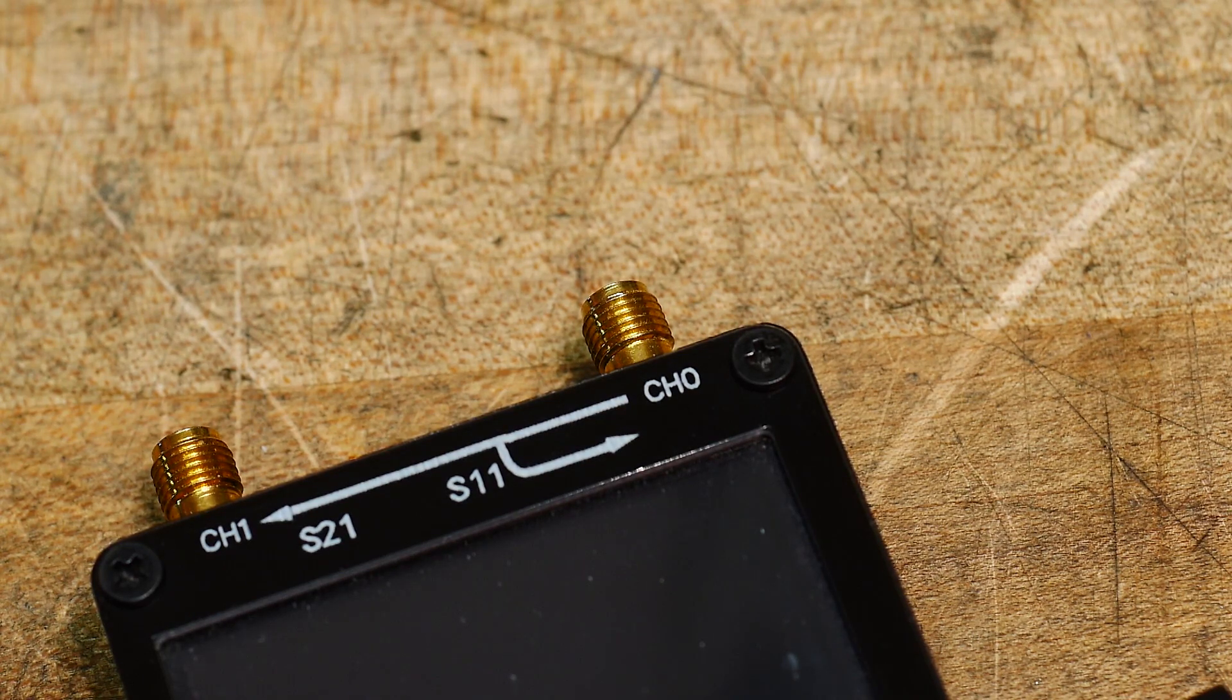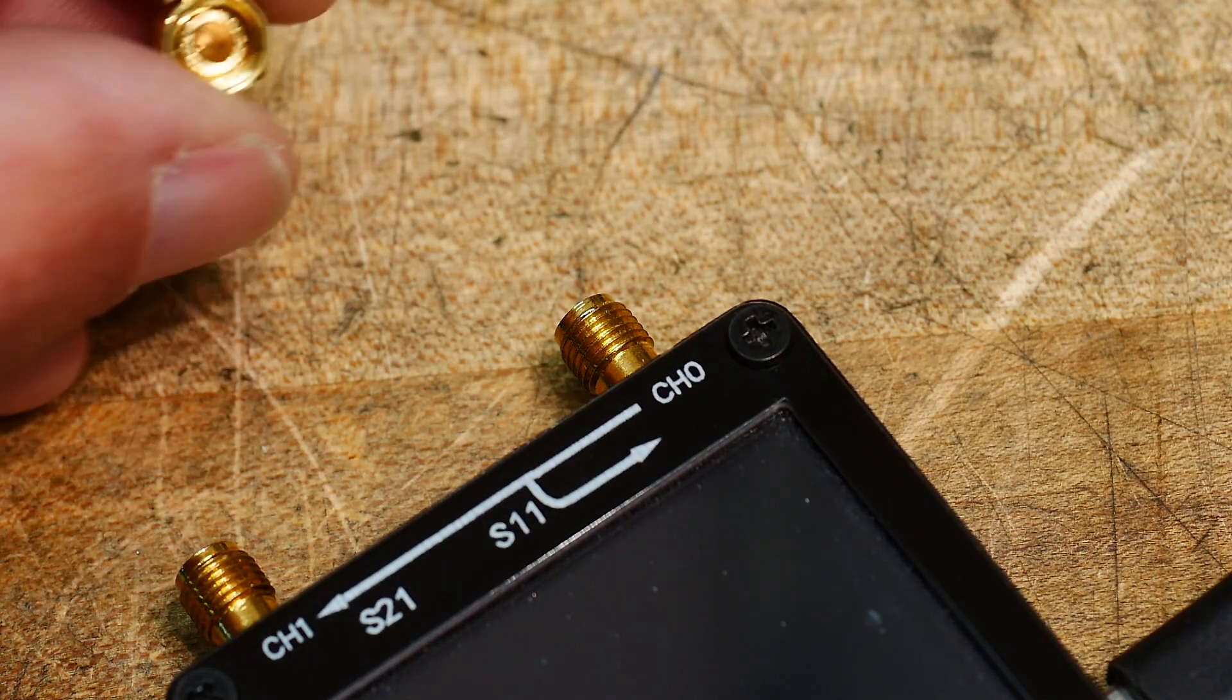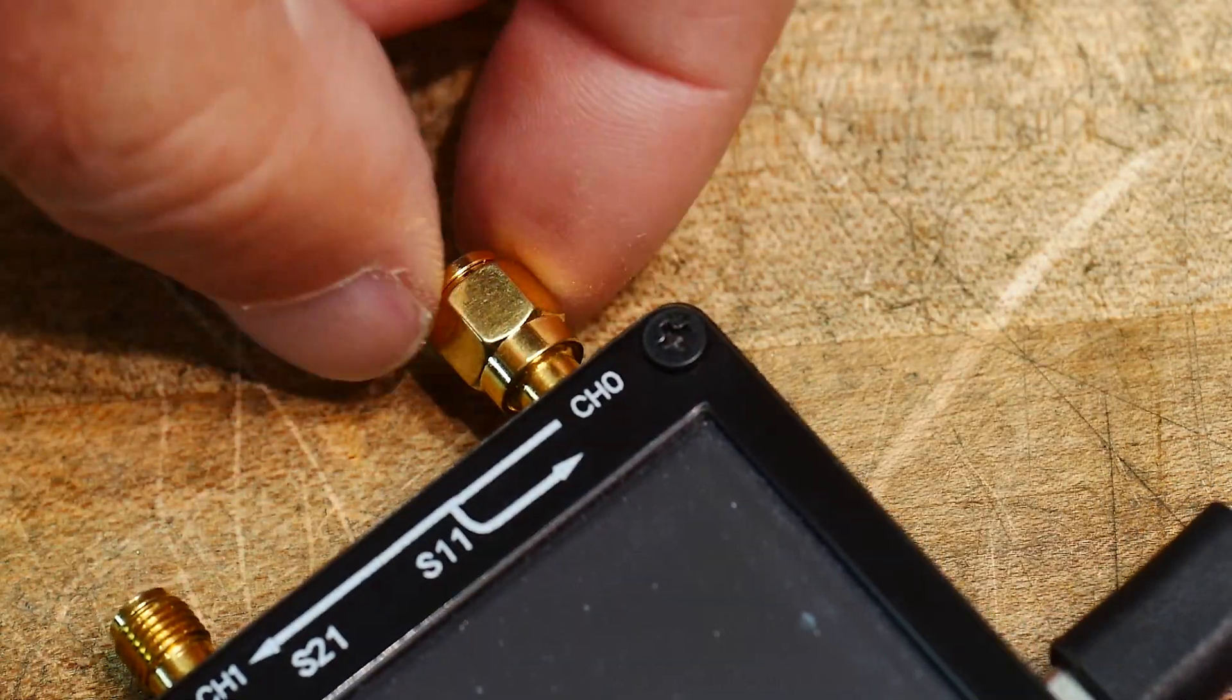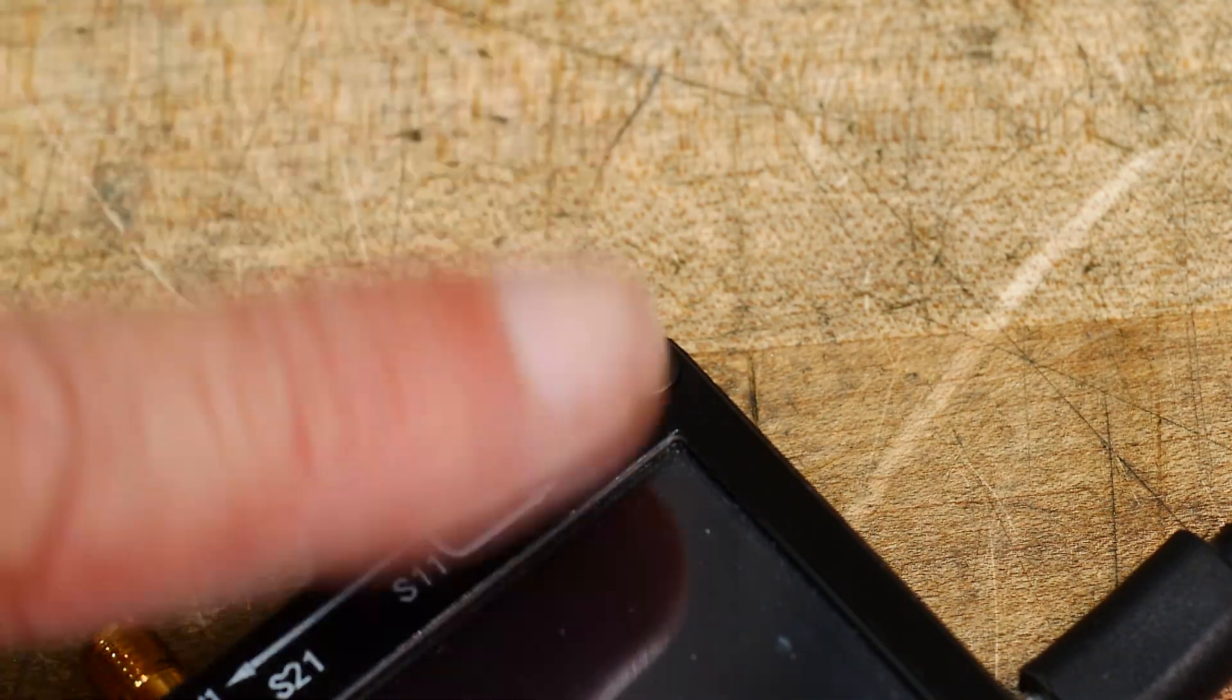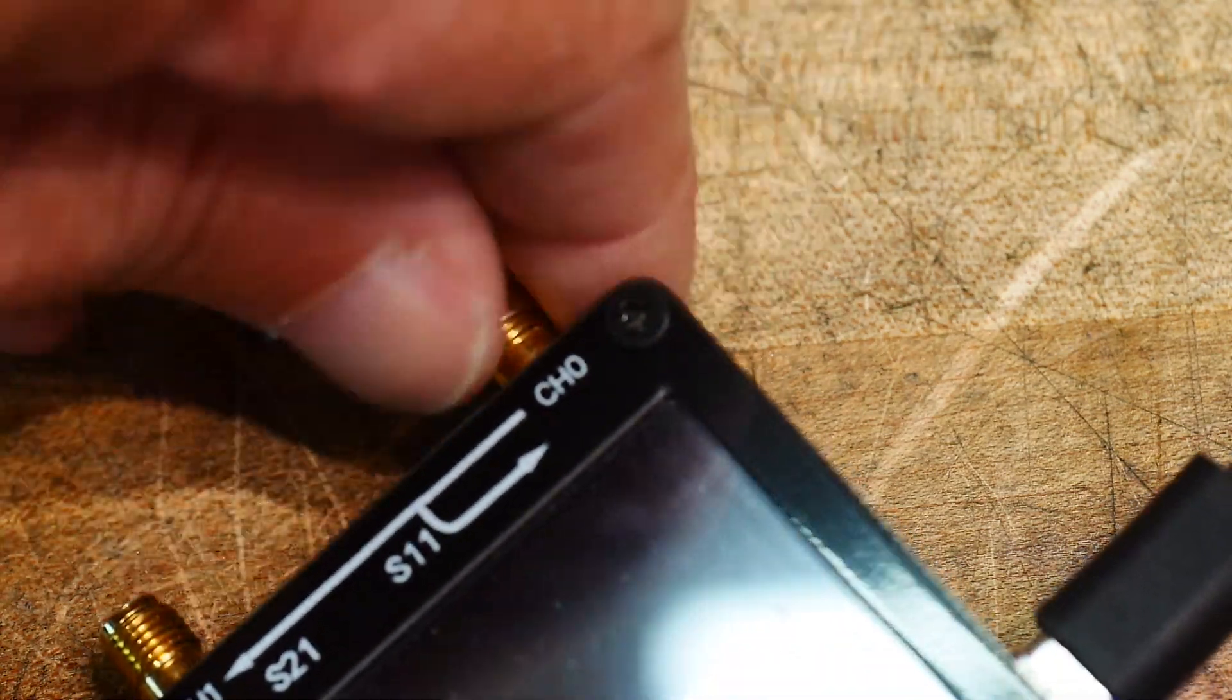So we're going to go through a calibration of the device. And during the calibration we need to attach these open shorts and loads. So how do we do that? Well we're going to screw them onto this connector, the channel 0. So if we're asked to use the open we'll take the open. We'll put it on the SMA and we tighten it down and we just hand tighten it. Looks like you can put a wrench on here. Don't do that. Just hand tighten it. Not too tight. But making good electrical contact. When asked to put on the short you do the same thing.